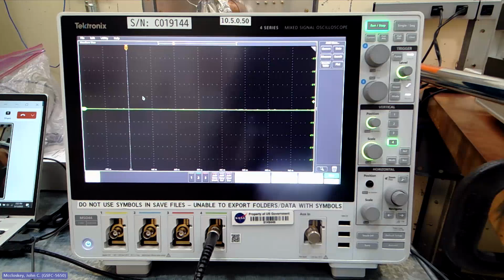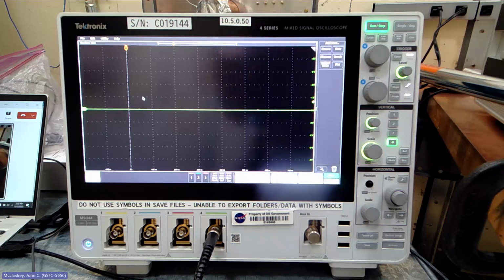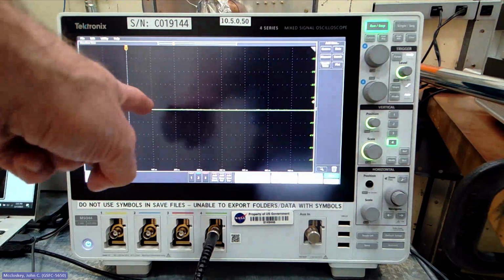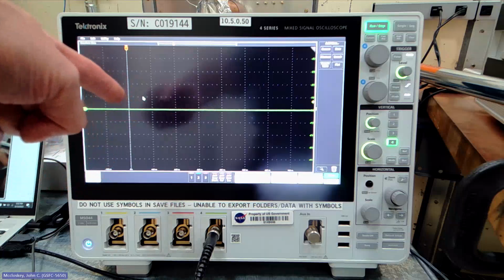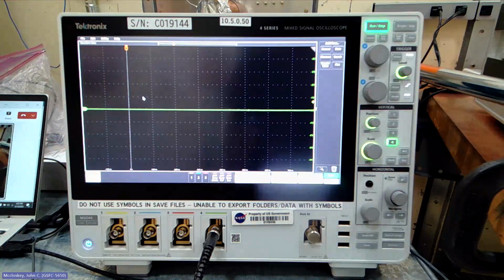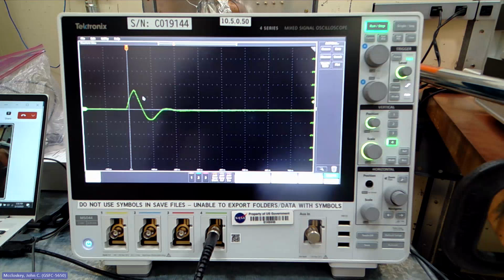So we're still just at that pre-calibrated level. So remember, we were getting 25 amps. So 2.5, or about 2.4 volts on the scope. So 2.4, well, going back through our 20 dB attenuator, that's 24 volts coming out of the current probe, which corresponds to 24 amps. So that's what we're getting with the shorter length of wire. Now turn our signal on, and that's what we get.